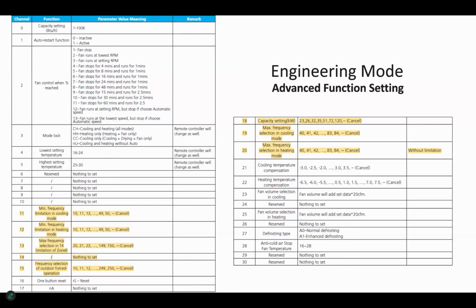That goes from, I believe, subtracting 40, out to plus 20 is the range on it. It goes in 1-step increments. Each step adds or subtracts 20 CFM. So if you need to add 100, you're going to set that to plus 5. That's on number 23 and number 25.